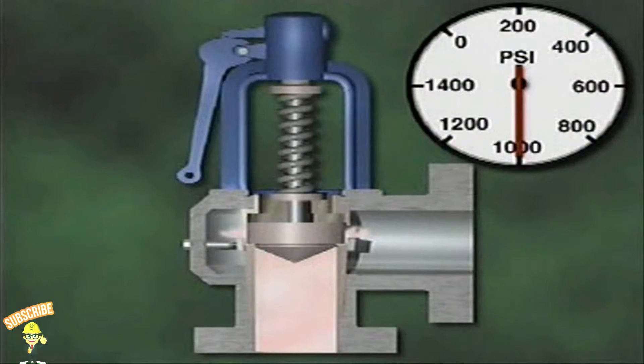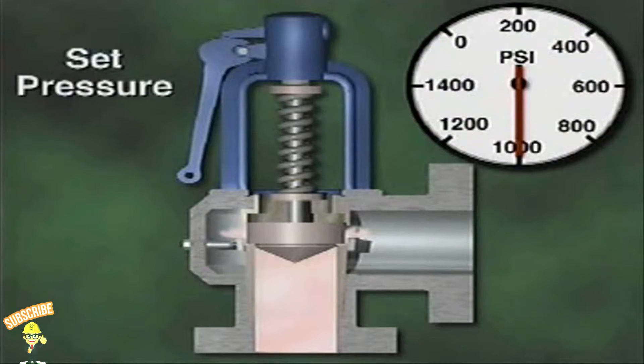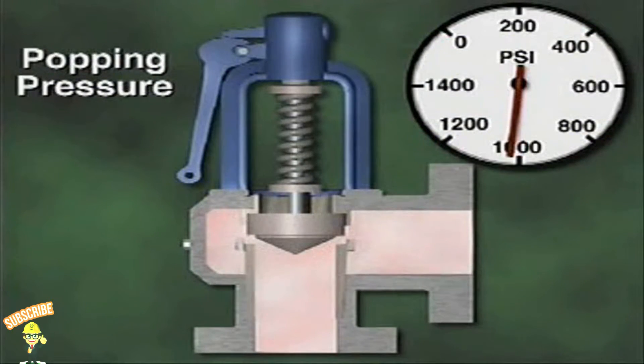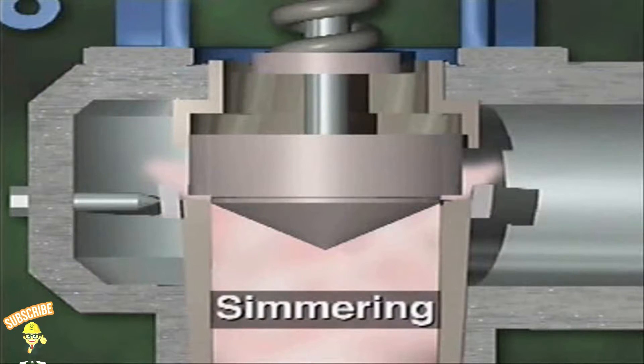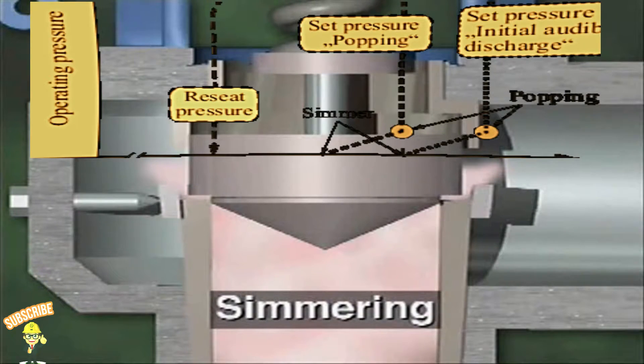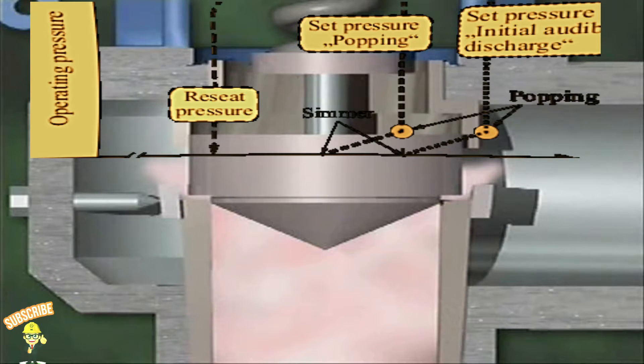The pressure at which the valve's disc begins to lift off the seat is called the valve set pressure. The pressure at which the valve actually pops open is the popping pressure. In most cases, simmering occurs briefly before a safety valve opens fully. During simmering, the disc is only slightly lifted and the valve discharges a small amount of fluid. Simmering lasts for only a fraction of a second until system pressure acts on the lip of the disc.